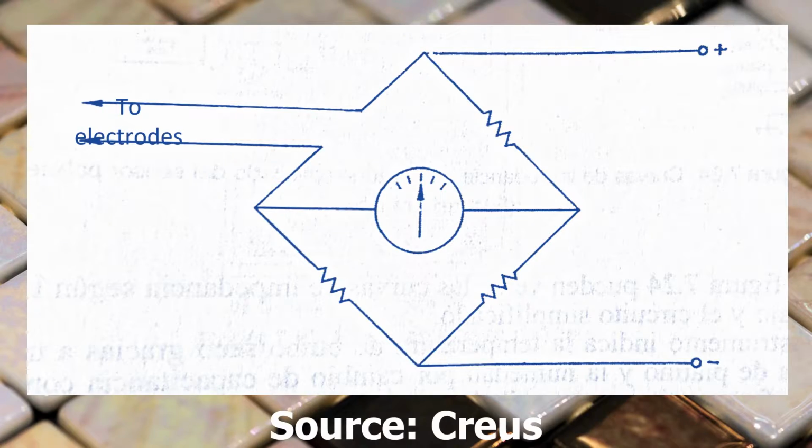The conductivity method is based on the measurement of conductivity of a product sample when a current passes through the contact electrodes with it. These electrodes are part of a bridge with humidity indication, recording, or monitoring. The method works well and is repetitive. However, the reading is considerably influenced by the state of the contact surface of the electrodes, by their pressure on the material, by the temperature, etc., in particular in high resistivity materials such as paper.